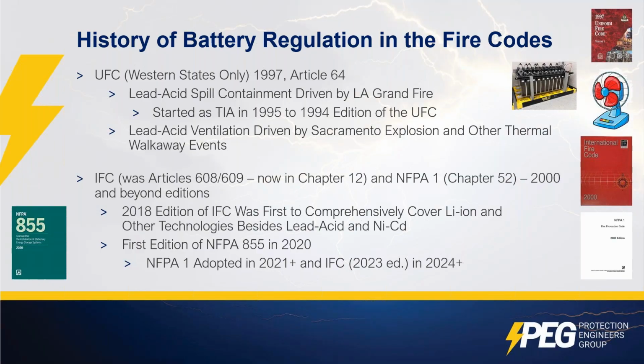In 1994, there was a fire at a Pacific Bell central office in Los Angeles. They call it the LA Grand battery fire, and it happened around one o'clock in the morning. Workers were making reconfiguration changes to the battery plant. They had installed temporary wires to one of the battery strings. A rectifier turned off, causing the battery to discharge unexpectedly, as it's supposed to do. But the wires that connected the battery to the plant were undersized and began to overheat and smoke and eventually caught fire. So it was a small fire, but it was somewhat disruptive, and it caused a 12-hour loss of 911 service to Los Angeles and some wider outages.